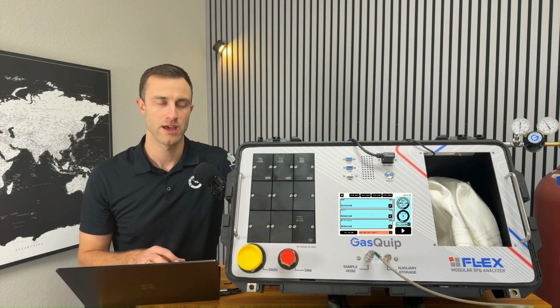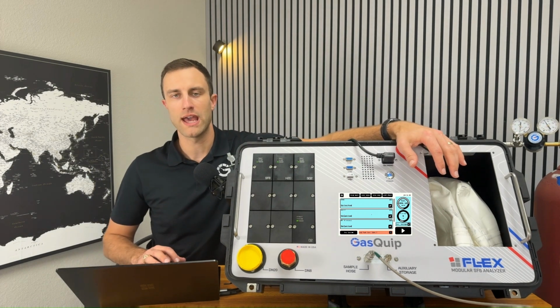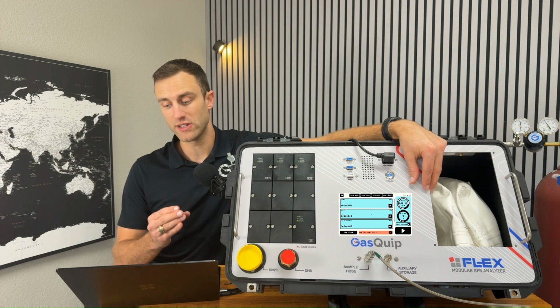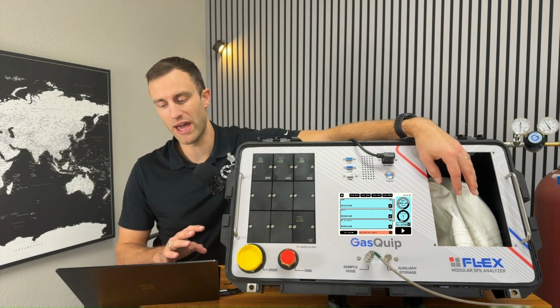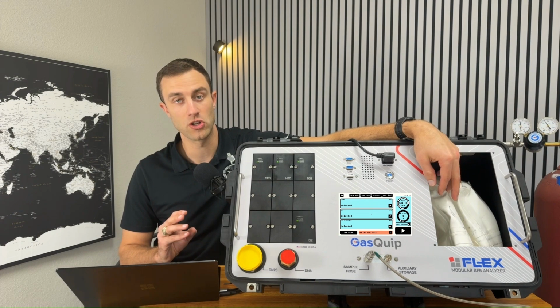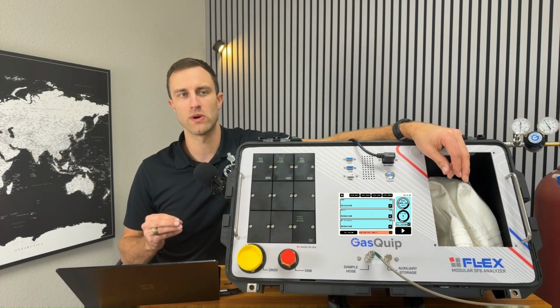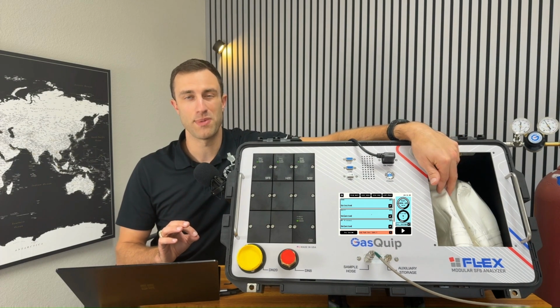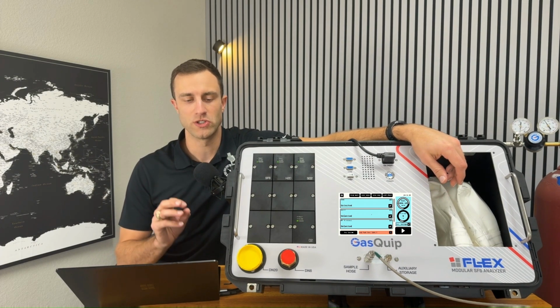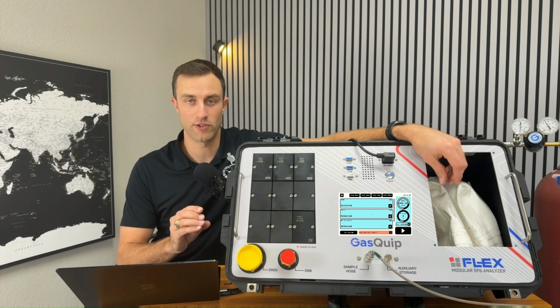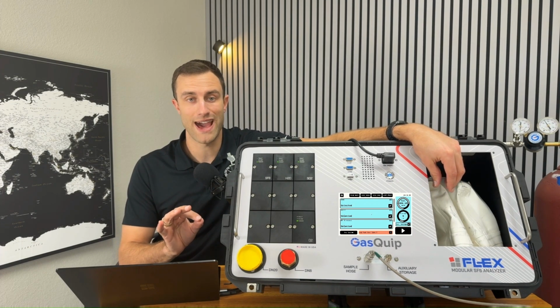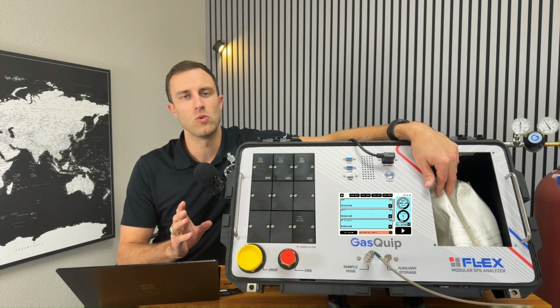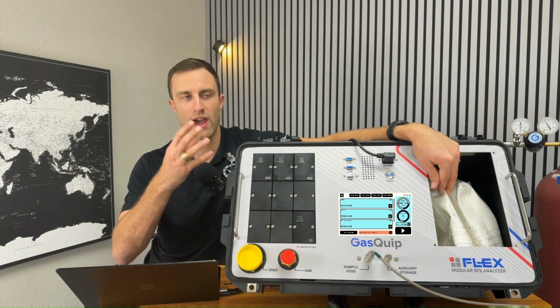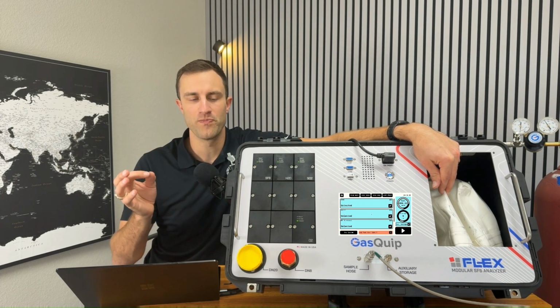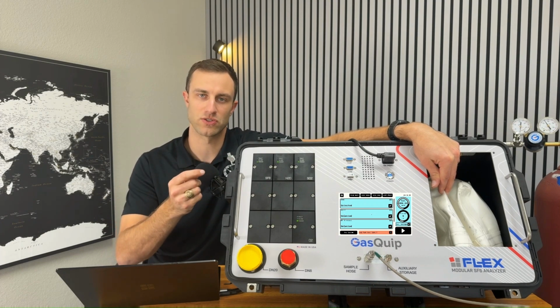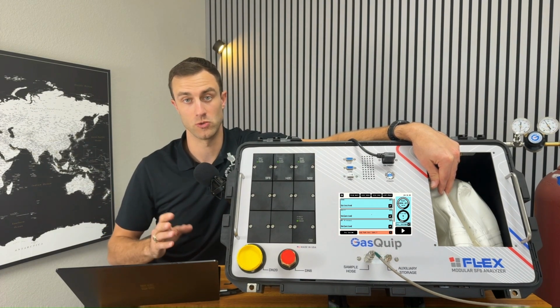The fifth way that I would check is to pull off the panel and run a test as normal, but visually inspect the bag. As you run a test, this bag should inflate with gas if you have a good enough flow. So if your test is showing a really low SF6 purity and basically a maxed out value on your H2O, which if you toggle through the units would be 0 degrees Celsius at atmosphere, then it could be likely that you are dealing with a low flow situation, where you have not enough gas going past the sensors, so they're spiking in the wrong direction of what you would like to see.